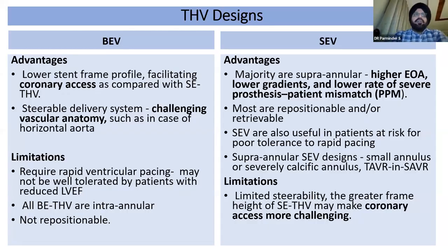So in a nutshell, if we look at the balloon expandable valves, these valves have a lower stent frame height, which facilitates coronary access in future. They have a steerable delivery system, which is good for challenging anatomies, as in tortuous vessels or a horizontal aorta. However, they require rapid ventricular pacing, so may not be suitable for patients with low ejection fraction. All balloon expandable valves are intra-annular, and the intra-annular position has been shown to have relatively inferior hemodynamics in comparison to supra-annular valves. There's no strong data on that, and balloon expandable valves do work well in the intra-annular position, but these valves are not repositionable. On the other hand, self-expanding valves are supra-annular.